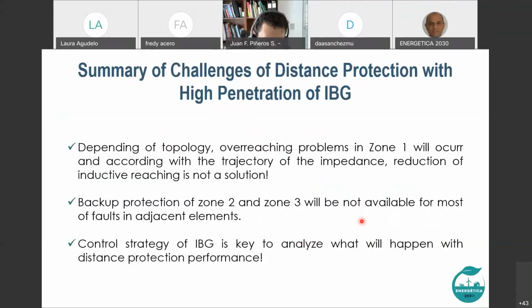Here are some conclusions, a summary of the challenges of distance protection with high penetration of inverter-based generation. As I told you, depending on the topology, and we were running several topologies, in general we will have problems with some overreaching, and it's important to say it's not coming from above. The overreaching is coming from the right, arriving down like an incursion, because you have a heavy load. The heavy load is because the inverter is adapting to the voltage, and if the voltage is low, it is pushing to keep the power flowing at low voltage, and this generates the overreaching coming from the right side of the impedance loop.